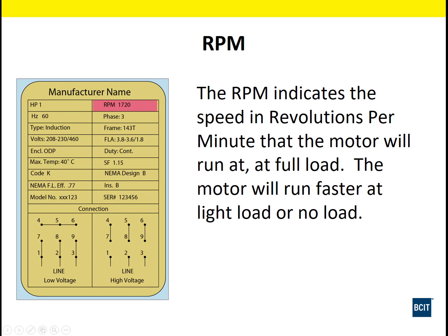Now we have RPM. On this nameplate it says 1720 RPM, and it's pretty obvious, that's the revolutions per minute that the motor will be operating at full load. So when this motor is putting out 1 horsepower onto the mechanical side of its connection, it's going to be running at 1720 RPM.